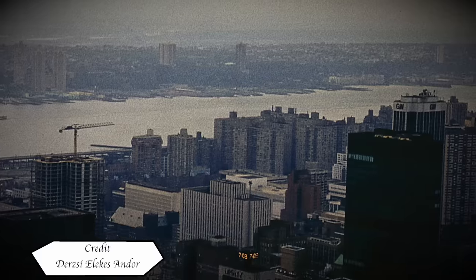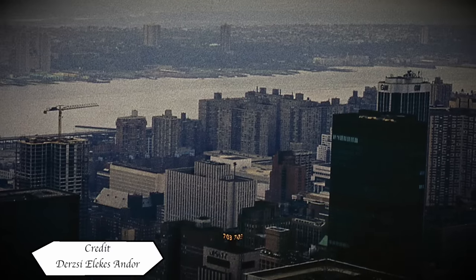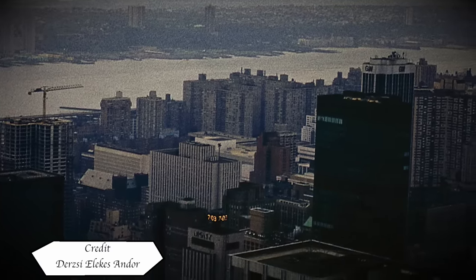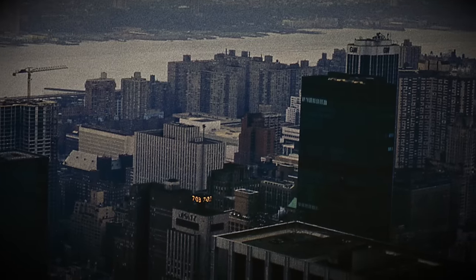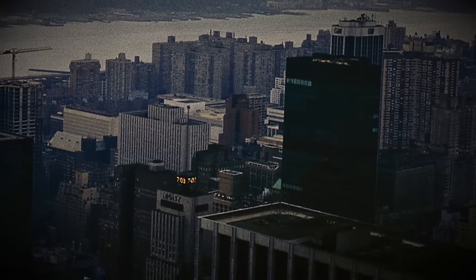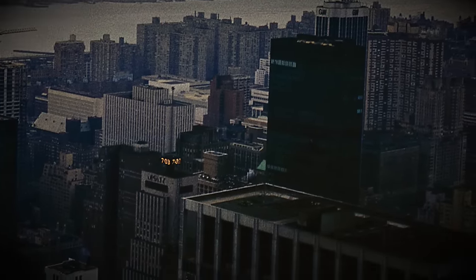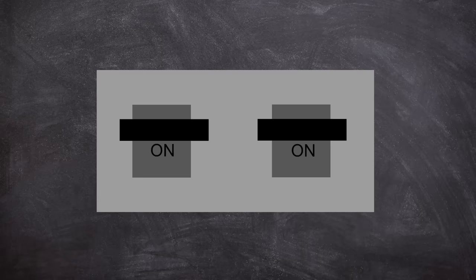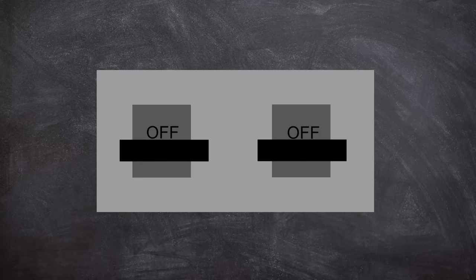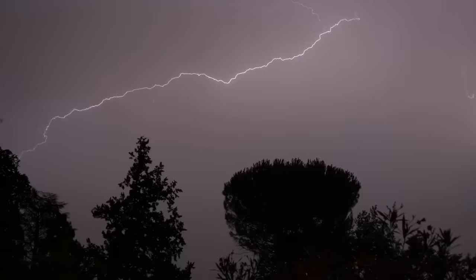This relatively normal but humid and warm July evening gave way to lightning. It lit up the sky. Lightning bolts reached out to the ground, and one of its targets was the Buchanan South substation. At roughly 9:17 in the evening, the strike blew out two circuit breakers. These didn't reclose as they were meant to. Obviously, this is not good, but not terrible. Lightning can't strike twice, right? Well, in today's story, also no.